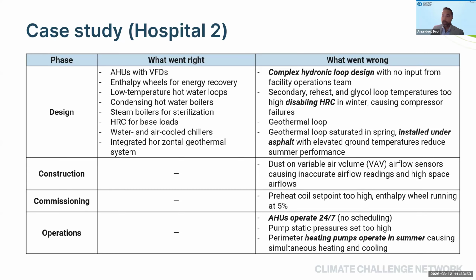The other thing, which is similar for most of the underperforming hospitals, is that the AHUs, the air handling units, are typically designed to have a setback schedule. However, they generally get operated 24/7. So that was a missed opportunity in this hospital as well. In addition, the perimeter pumps ran in summer, which resulted in simultaneous heating and cooling in the system, increasing the cooling as well as the heating energy in the building.